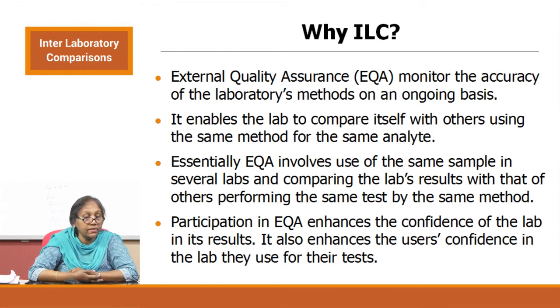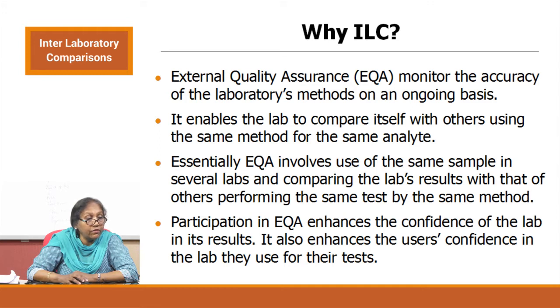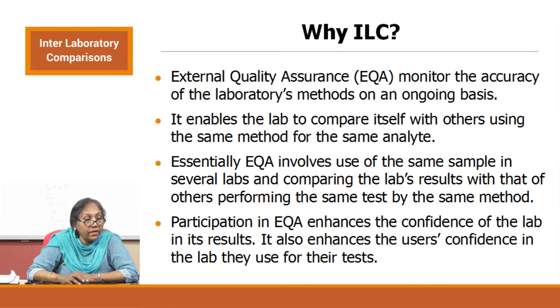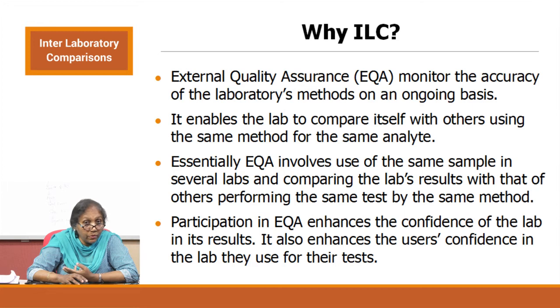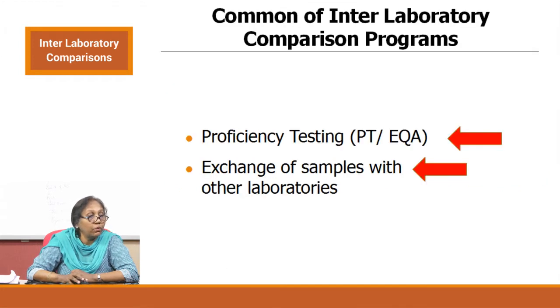Why interlaboratory comparisons? External quality assurance monitors the accuracy of the laboratory's methods on an ongoing basis. It enables the lab to compare itself with others using the same method for the same analyte. Essentially, ILC involves the use of the same sample in several labs and comparing results with others performing the same test by the same method. Participation enhances confidence in results for both the lab and its users.